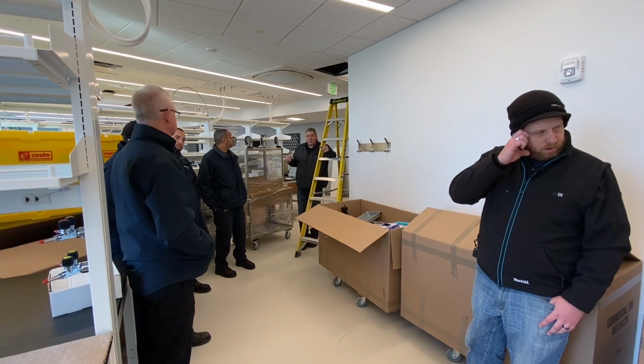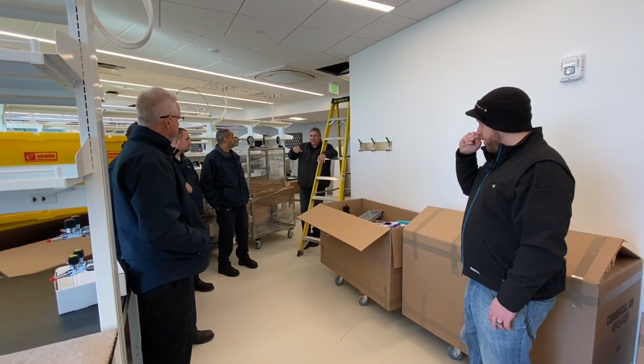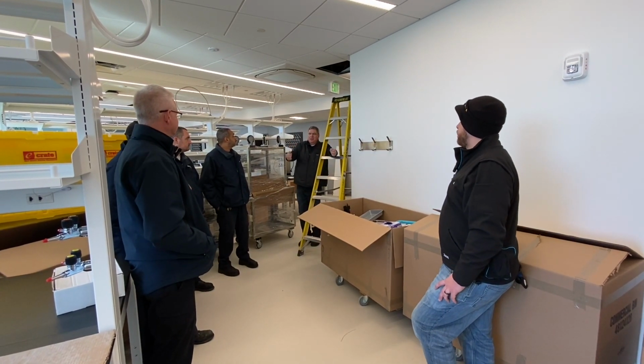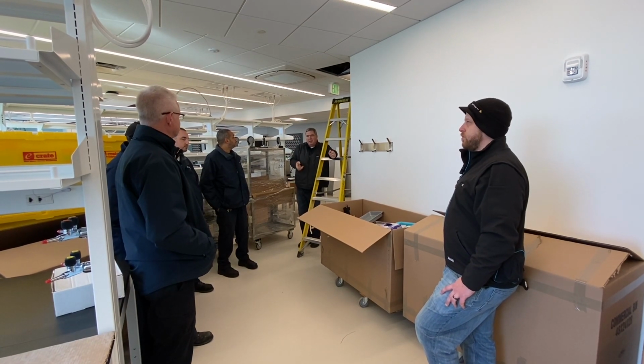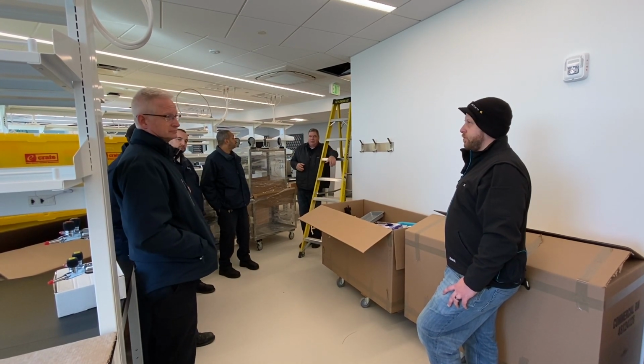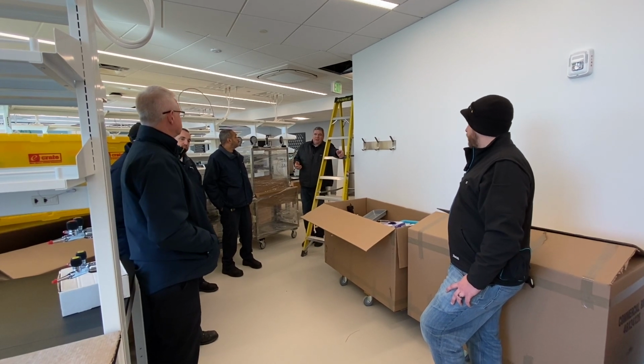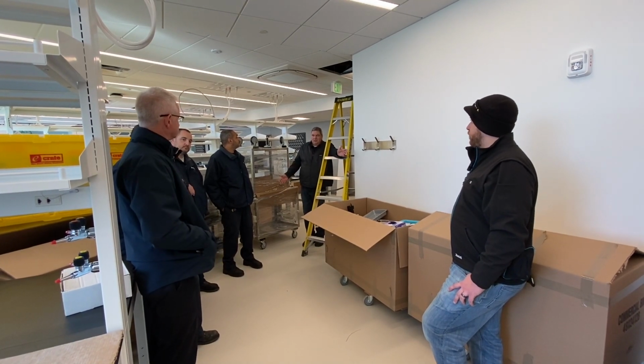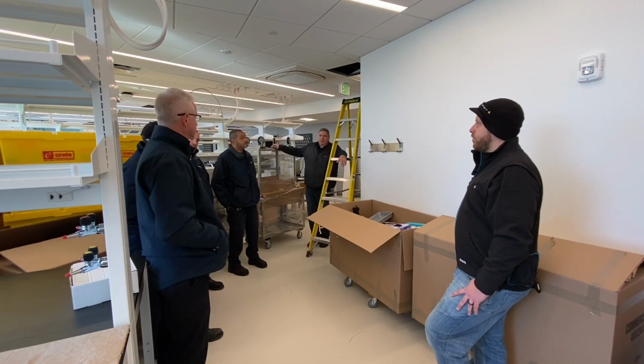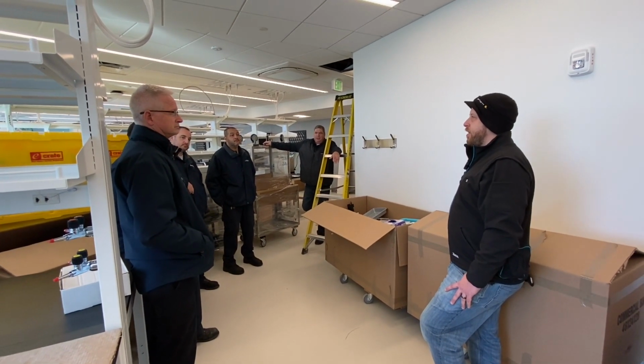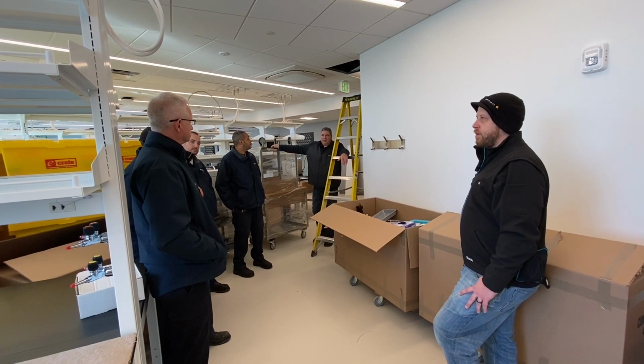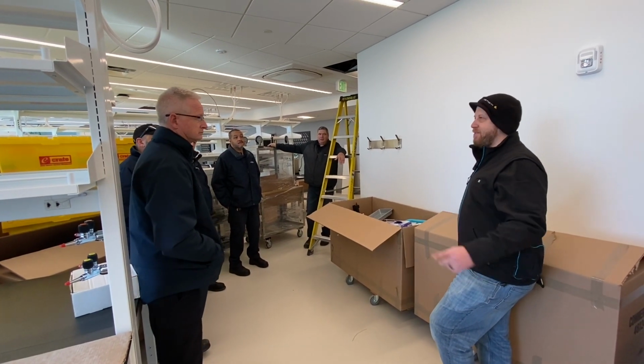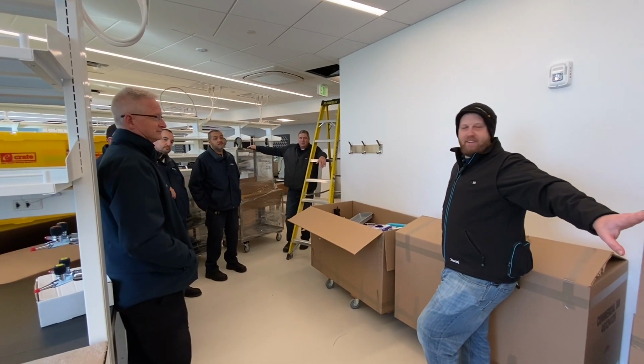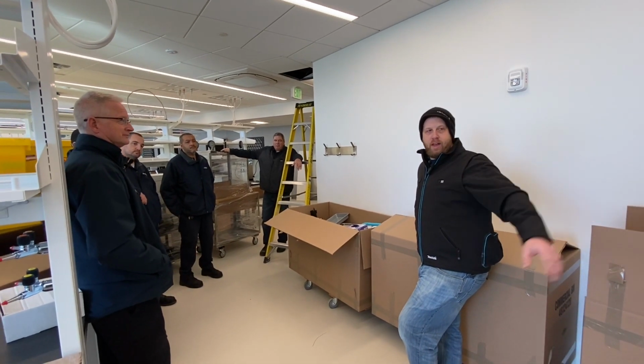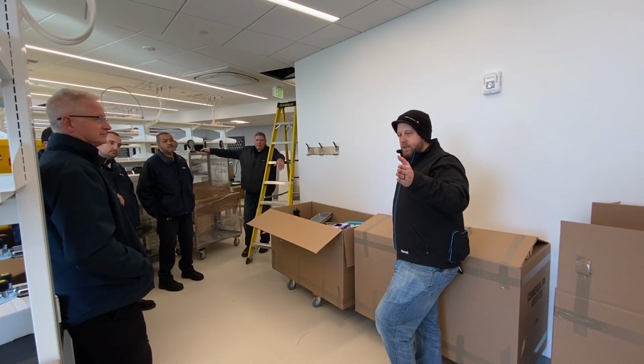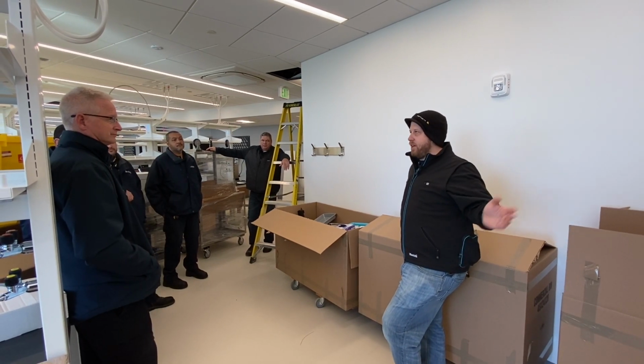Or they bypass the hood sash. They do that a lot of times because they're trying to put a bigger instrument in. So those are things I would look at first, and then if that all clears, that's when you get involved. They'll ask you questions. There are a few times where we come in and all of a sudden they've put an oven in there, taking up a lot of the area across the hood, and it's struggling. So there's also that.